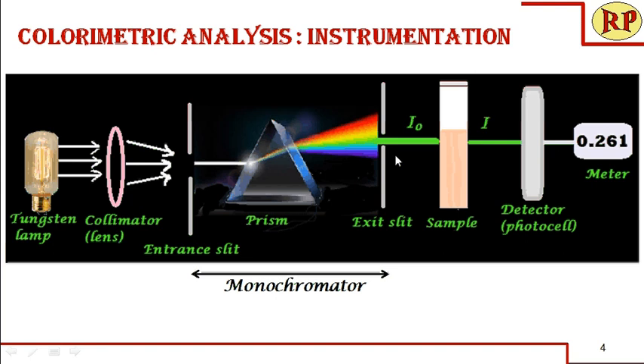What is the role of a monochromator? It absorbs all the light except the chosen wavelength. We choose one particular wavelength depending on the absorbing substance. Here we have taken a prism, though we can also use a diffraction grating. This splits or disperses the white light into the visible spectrum — VIBGYOR. Through the exit slit, only the chosen wavelength comes out and all other wavelengths are absorbed.